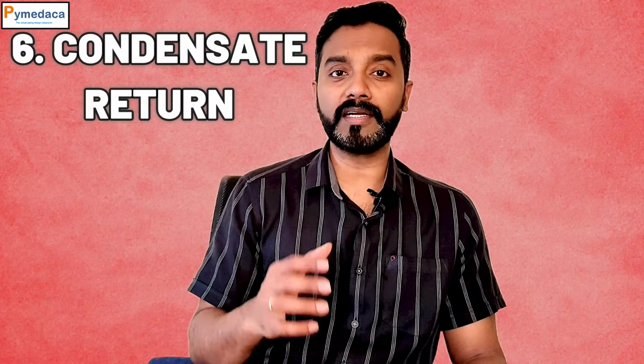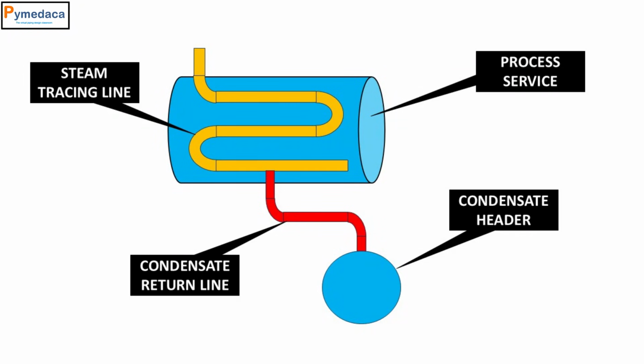And the last important thing is the condensation return, because when you pass steam over these heat tracing coils, naturally, because of the heat loss and the pressure loss, a certain amount of condensation will form. This condensation needs to be removed. If you don't remove the condensation, it will block the piping. So you need to provide a provision to remove the condensation, and to return this condensate to the condensate header. So this is a continuous system. Like for any steam system, you will have the main steam system as well as the condensate system. You will be able to achieve it by discussing with the process engineers.